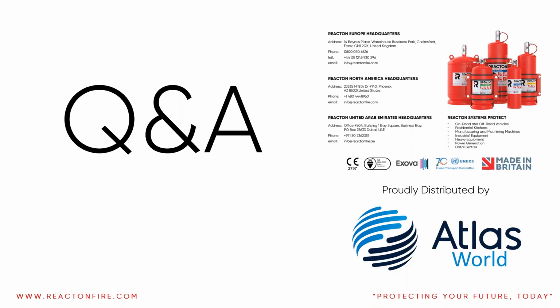Okay. I think you touched on this one earlier. There's a question from Washington. Can this be interfaced to a fire alarm system for notification? Yeah, absolutely. Every system can have what we call a pressure switch mounted onto either the valve head itself or onto the end of the detection tube. So once a pressure loss is initiated inside the valve, the pressure switch will kick into action and send an electronic pulse to an existing fire alarm inside a building. Very simple to do.